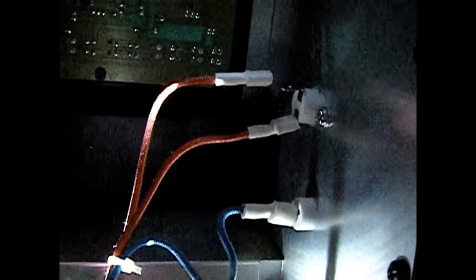Up there is what causes the E1 error code. And I just pulled that wire off there to show you that that thermal circuit breaker is what causes it. If it opens, it will cause the error code.